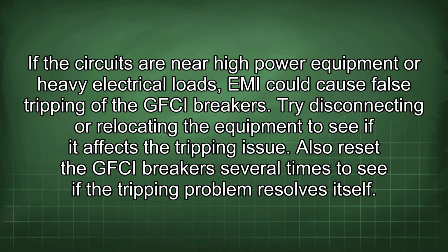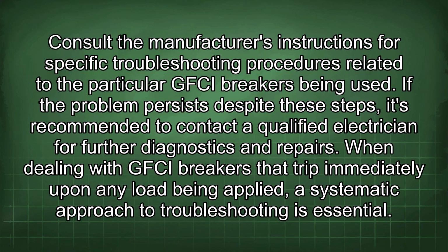Also reset the GFCI breakers several times to see if the tripping problem resolves itself. Consult the manufacturer's instructions for specific troubleshooting procedures related to the particular GFCI breakers being used. If the problem persists despite these steps, it's recommended to contact a qualified electrician for further diagnostics and repairs.